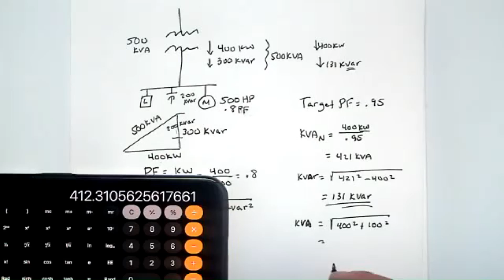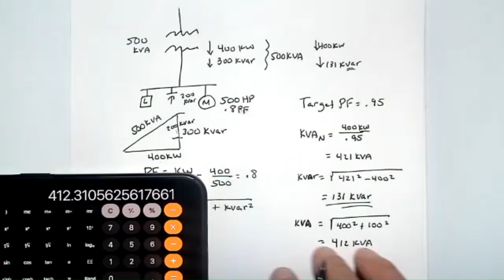Well, if I put a 200 kVAR capacitor in there, now my new kVA is kilowatt squared, so 400 squared, plus 300 minus the 200 that I'm putting in there, so plus 100 squared. My new kVA, 400 squared plus 100 squared, and then take the square root of that, 412 kVA.